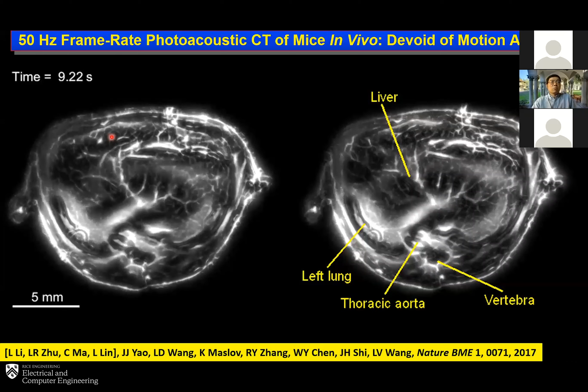But you can see if you have a lower speed, you may run into problems, especially in the region where the breathing motion causes large scale motion. If you sample at a lower rate, all this motion can blur your image. All those factors combined allowed us to get a good image. I don't have time to talk about the detailed image reconstruction. In fact, we use dual speed image reconstruction because the coupling medium has a different speed of sound than the biological tissue. If you account for that speed difference, the image quality improves.